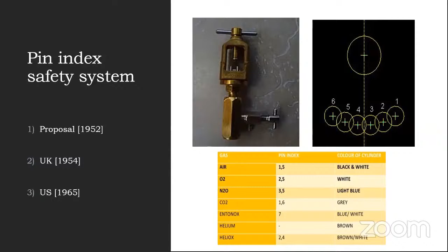For example, oxygen is 2,5. So the oxygen cylinder will have a depression at the points corresponding to 2 and 5, which will match with the pins on your pin index. So the cylinder will be connected. It can only be connected if it matches the pin, and the yoke holds it in place and sufficiently presses when the yoke hanger is tightened on it.